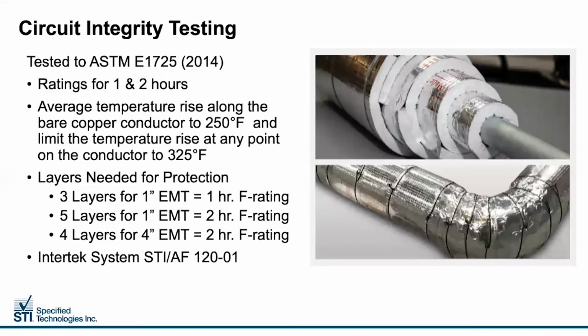EWrap uses a system of layering to achieve a desired hourly rating. 3 layers are required, each about a half inch thick, for conduits of 1 inch for 1 hour of fire resistance. For conduits sized 4 inches and down, 5 layers are required for a 2-hour fire resistant rating. For conduits greater than 4 inches, only 4 layers of EWrap are required to obtain 2 hours of rating.